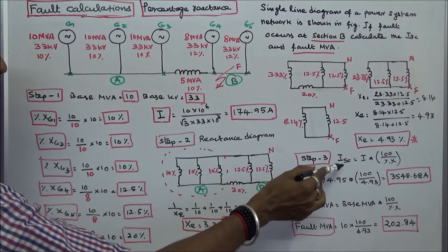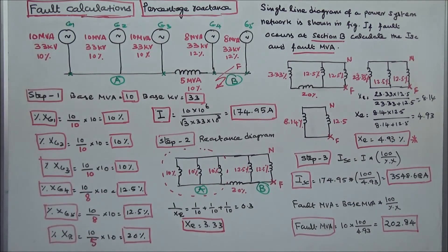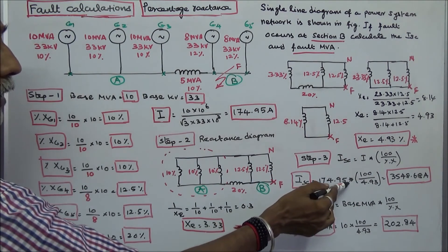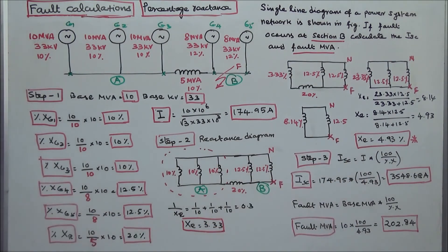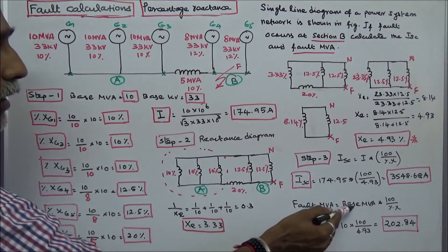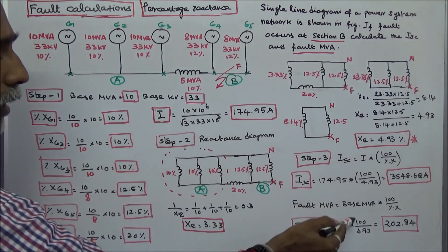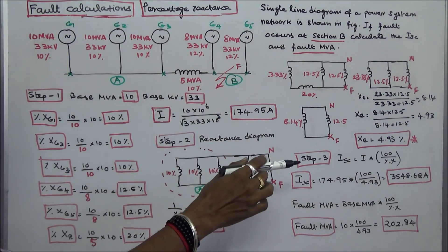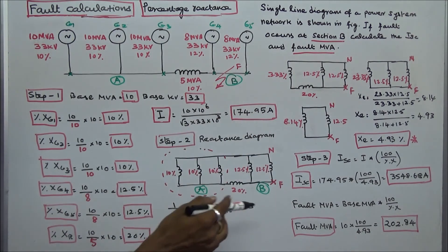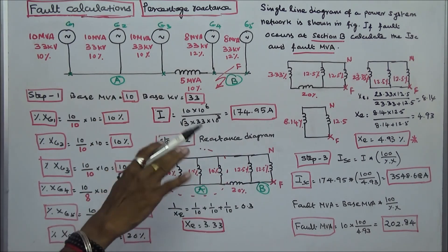Step 3: Calculate the short circuit current. The formula is I_sc = I × 100 / percentage X. I_sc = 174.95 × 100 / 4.93 = 3548.68 amps. Fault MVA equals base MVA × 100 / percentage X = 10 × 100 / 4.93 = 202.84 MVA. Therefore, short circuit current is 3548.68 amps and fault MVA is 202.84. Thanks for listening.